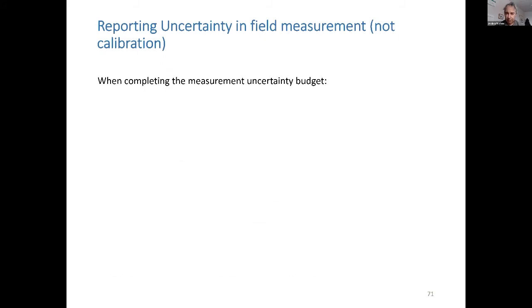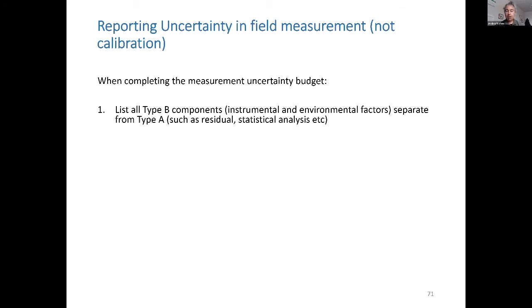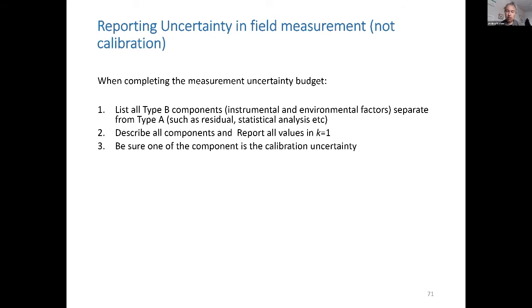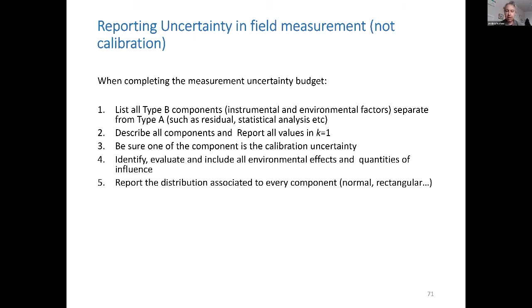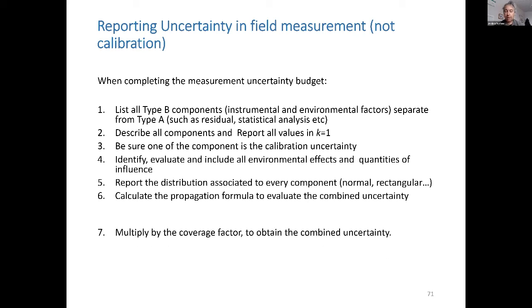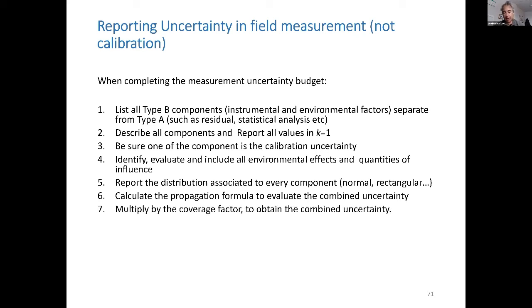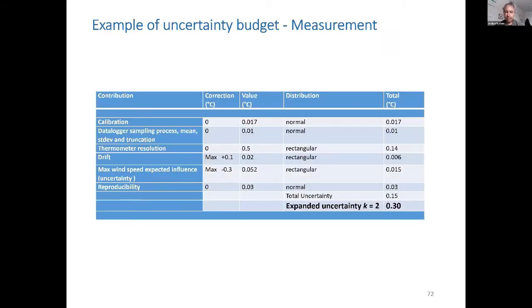For reporting at the field measurement, you have to list all the components, describe them in K1. Be sure 1 is the calibration uncertainty. Don't even start if you don't have it. Identify the environmental effect as well as you can. Tomorrow we will see it's a nightmare. Report the distribution, as we have seen in the table before. Calculate it with the square root and the derivative. Multiply at the end by the coverage factor K to obtain the combined and more representative uncertainty.